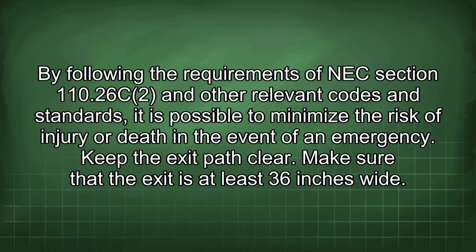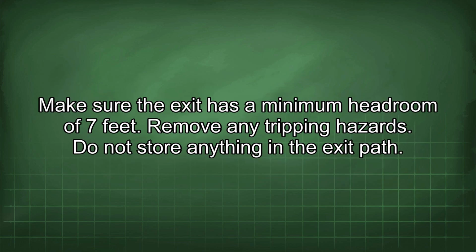By following the requirements of NEC Section 110.26C2 and other relevant codes and standards, it is possible to minimize the risk of injury or death in the event of an emergency. Keep the exit path clear. Make sure that the exit is at least 36 inches wide. Make sure the exit has a minimum headroom of 7 feet. Remove any tripping hazards. Do not store anything in the exit path.